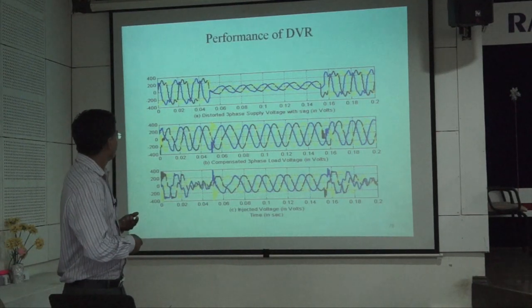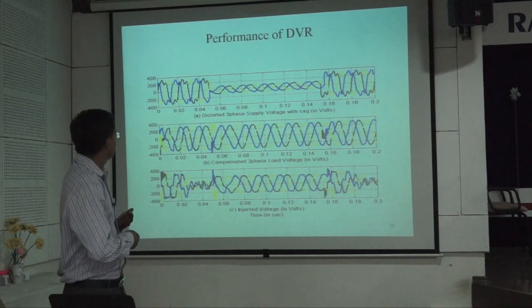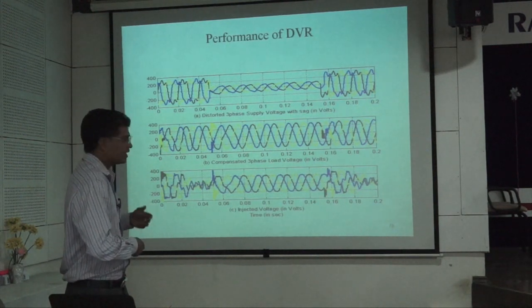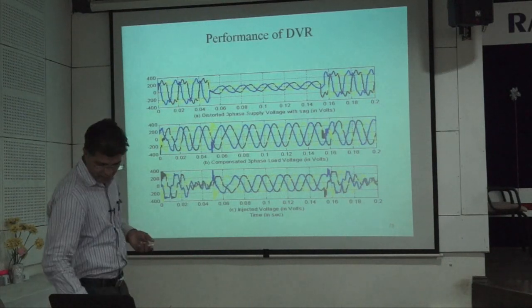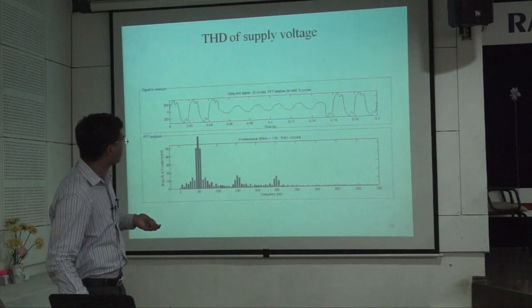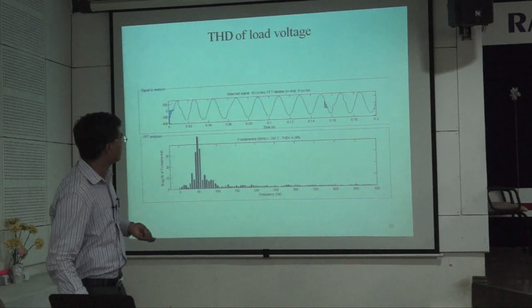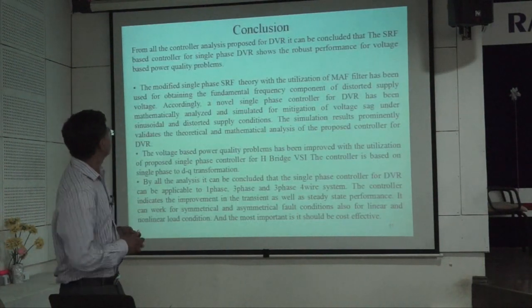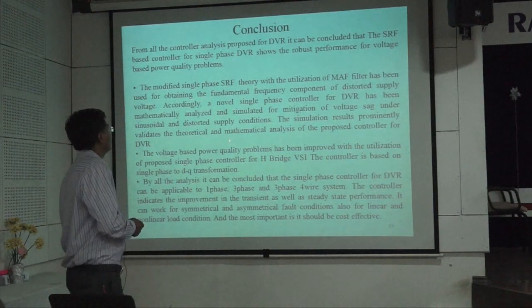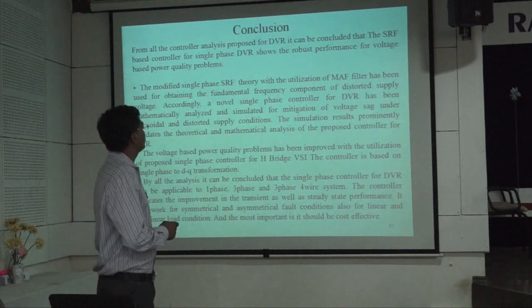This is the injected voltage when there is no sag. It is giving the transients. It is taking near about 1 cycle to be in action. The THD is again reduced in this case also to 4.34%. The conclusion from all the controller analysis: there are 3 controllers that have been designed for DVR.